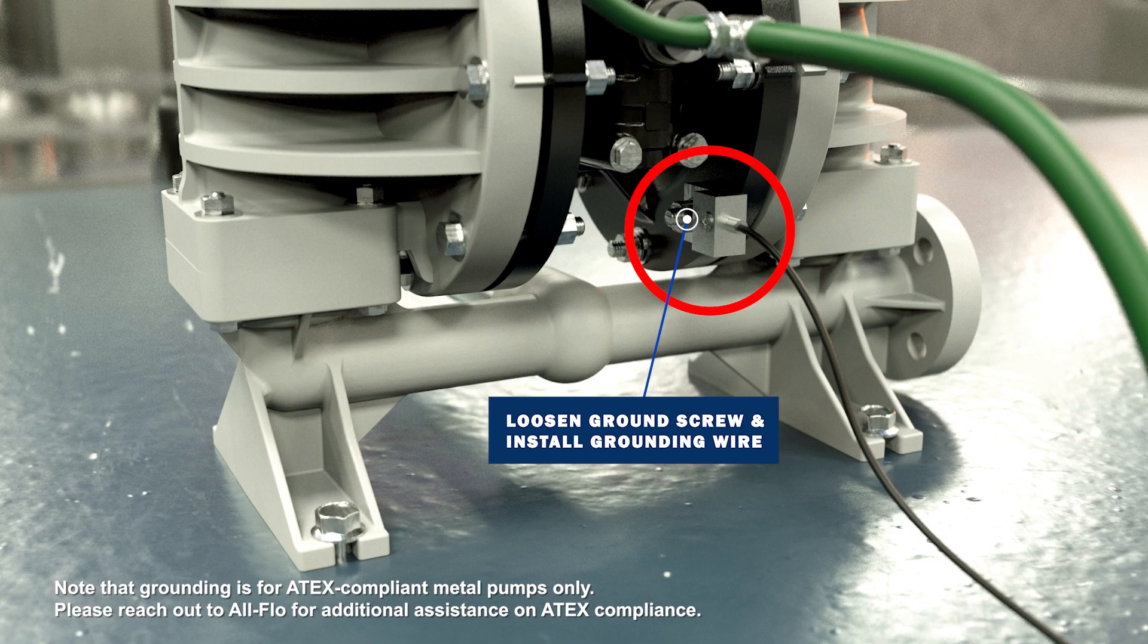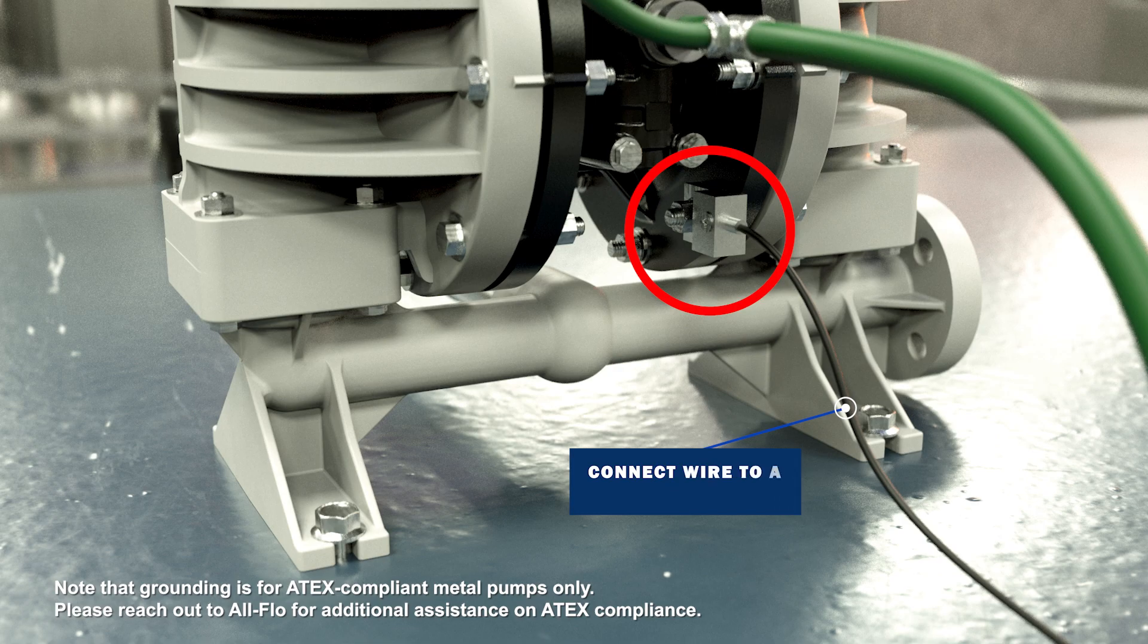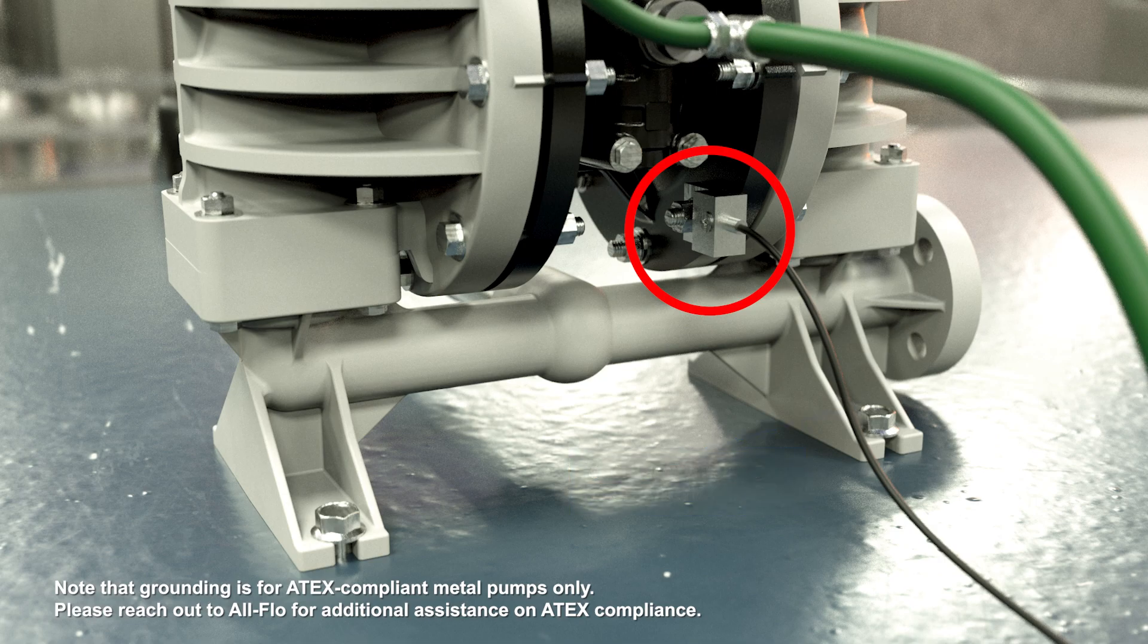The wire should be a 12 gauge wire or larger. Connect the other end of the wire to a true earth ground. The equipment must be grounded to achieve ATEX rating displayed on the pump's tag. It is recommended to configure the pump with the grounding lug option.